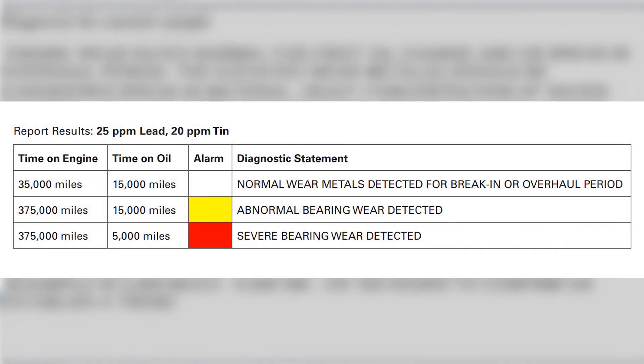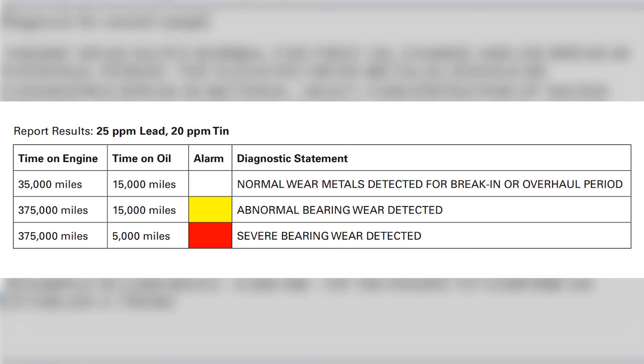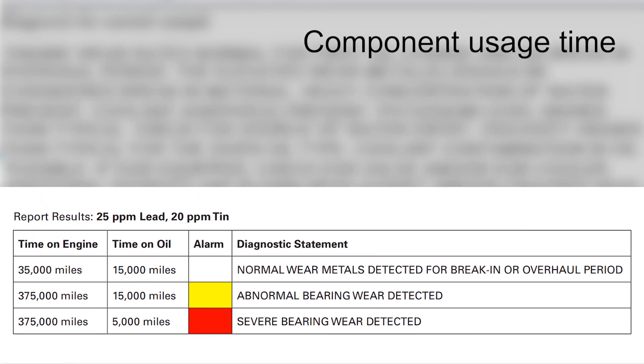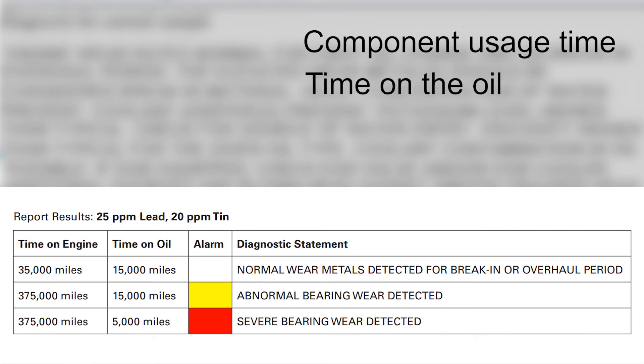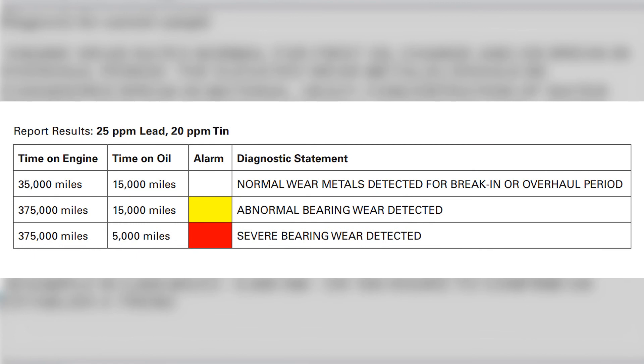The expert system also grades the sample results as normal, abnormal, and severe, using color-coded alarms. The system automatically adjusts the alarm code based on usage time on the component, time on the oil, and break-in periods. So from this example, you can see that the same analytical results of 25 ppm of lead and 20 ppm of tin will give different alarm statements based on these factors.